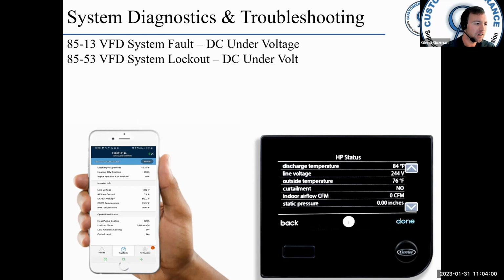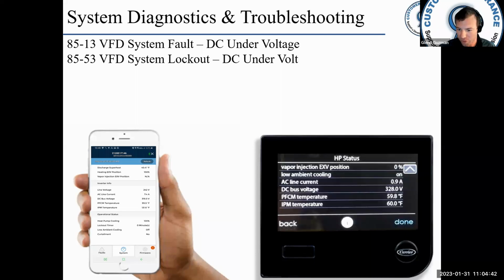We have seen some issues with this fault and the compressor backspin. So I'm not going to beat around the bush on that one. If you guys are seeing this fault and your compressor doesn't sound quite like you think it should, reach out to us and we'll cross that bridge when we get there. But I would definitely check some of the most obvious stuff first: connections, line voltage to, line voltage out of the drive, that sort of thing. Check your reactors, make sure they're plugged in, power cycle the unit, and check some of those normal things before reaching out to us.